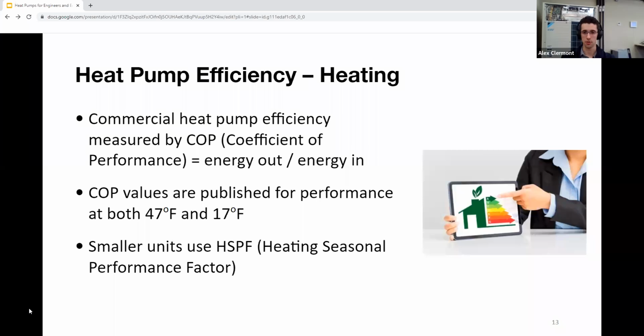Unfortunately, there's also no part load COP, and it's similar to EER in cooling as it measures the heating capacity at full load. Now, ideally, there'd be an ICOP, which could look at part load COP. Now, there's also HSPF, which stands for Heating Seasonal Performance Factor for smaller systems, which looks at the heat output for a heat pump, and that's similar to SEER, but for heating.